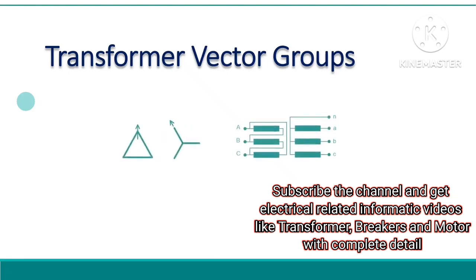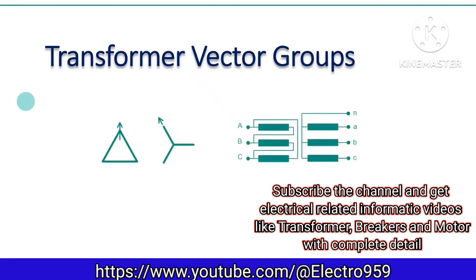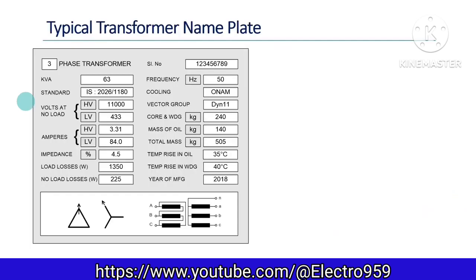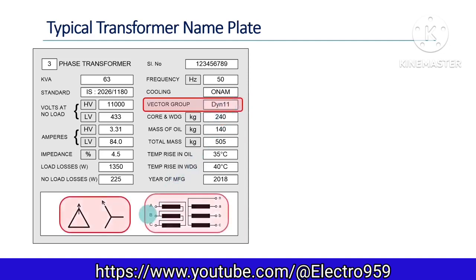In this video, we are discussing vector groups in three-phase transformers. First, have a look at the typical nameplate of a three-phase transformer. The details printed on the nameplate include the KVA rating, the voltage on the primary and secondary sides, the currents, the percentage impedance, the frequency of operation, type of cooling, the weight of the transformer parts, and the possible temperature rise. In addition to all these things, the vector group is also specified — here it is given as dyn11. We also have graphic symbols printed on the nameplate that are related to the vector group designation.